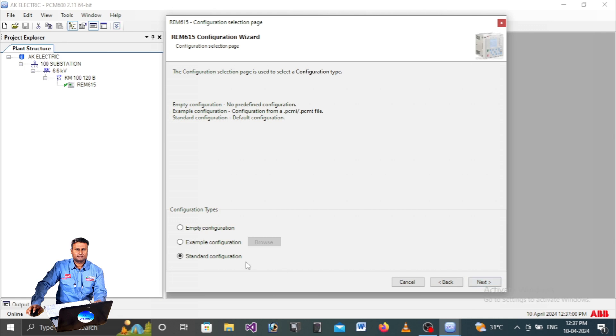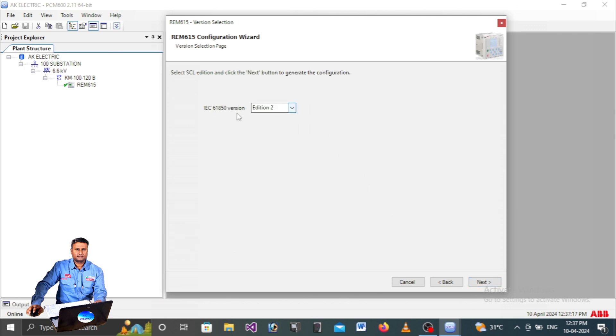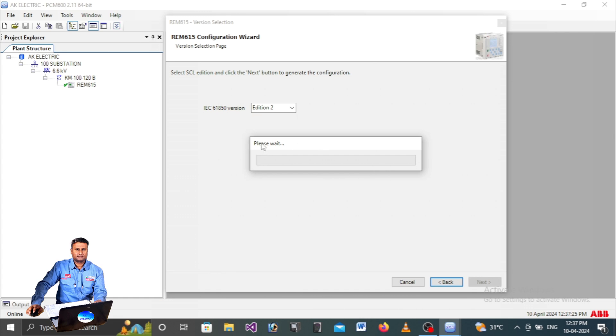Proceed to the next step. You will see three configuration options - for example, standard. Select the standard configuration and click Next. The IED is working under Edition 2, so proceed with Edition 2. Now PCM600 is communicating with the relay and downloading configuration data. Wait for the status bar to complete.